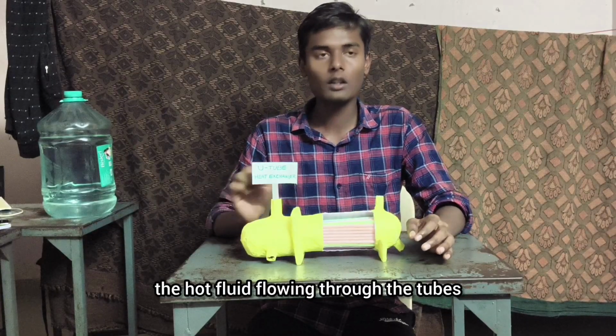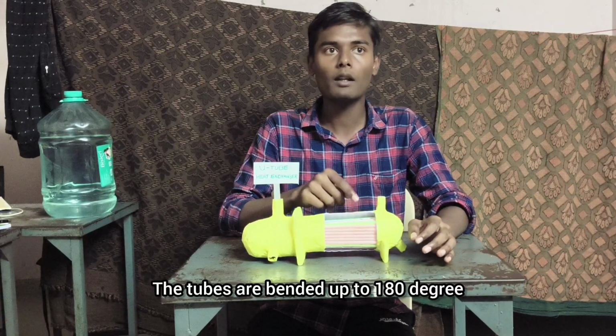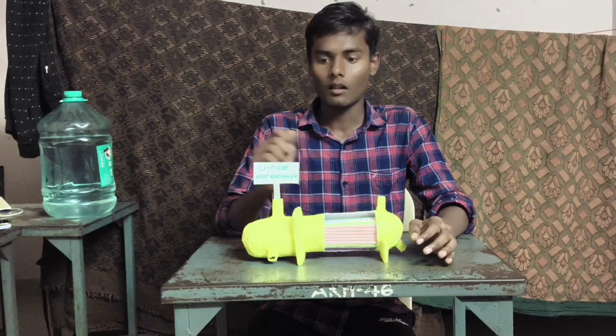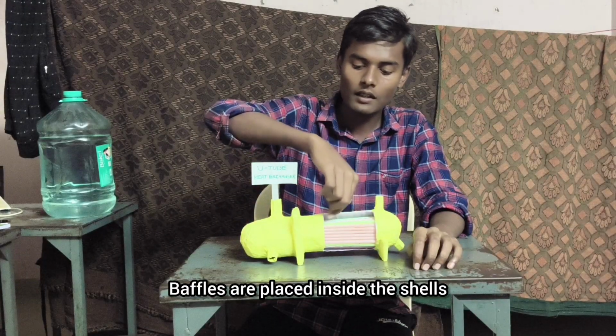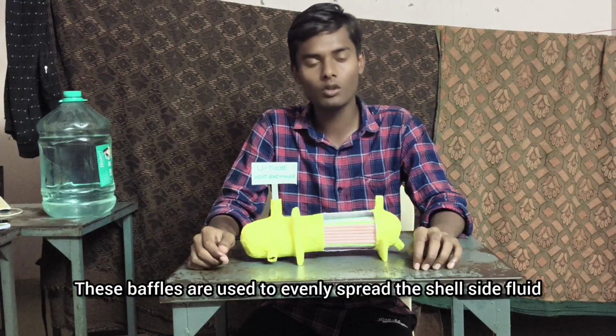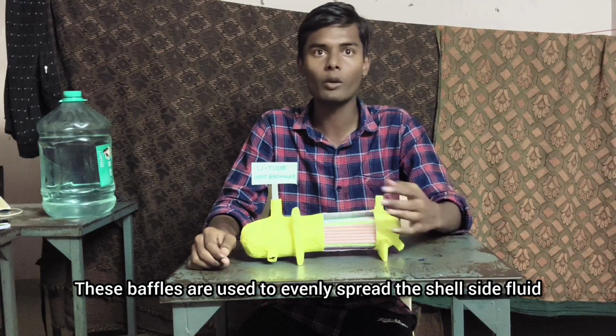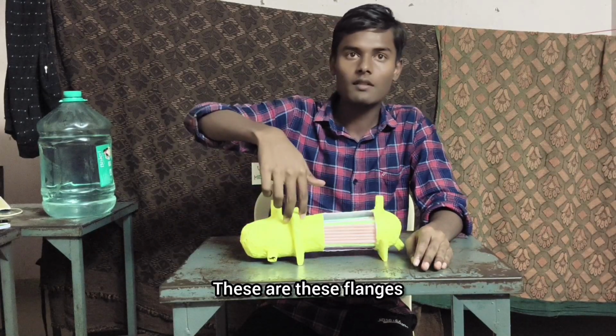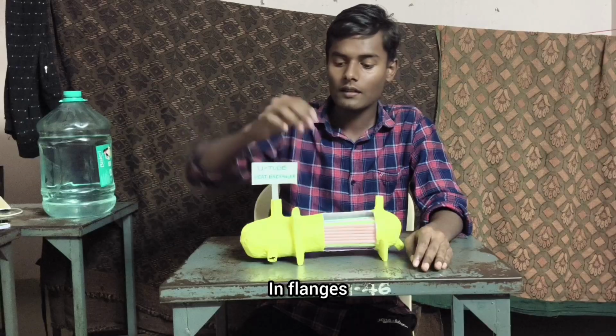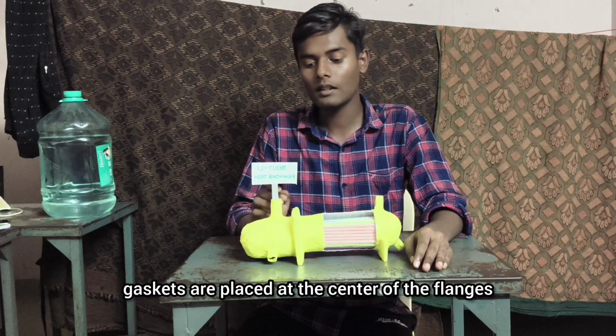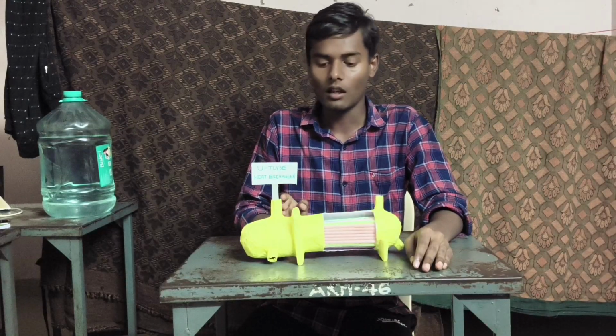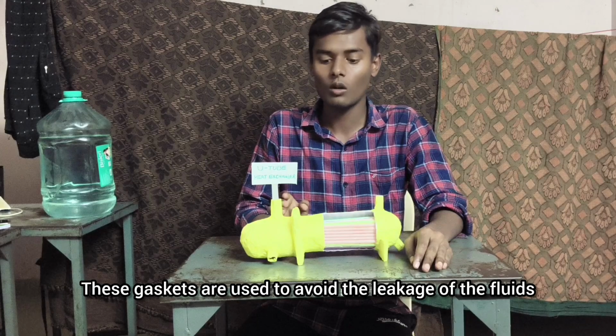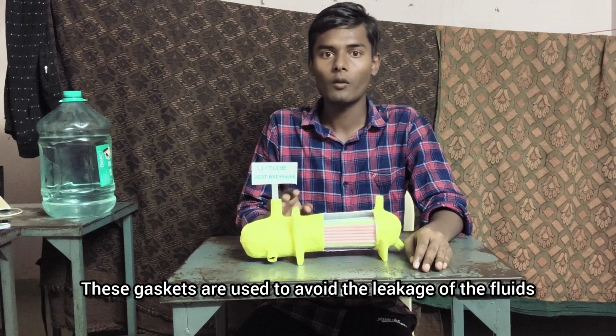The hot fluid flows through the tubes. The tubes are bent up to 180 degrees. Baffles are placed inside the shell. These baffles are used to evenly spread the shell side fluid. These are the flanges. In the flanges, gaskets are placed at the center. These gaskets are used to avoid the leakage of the fluids.